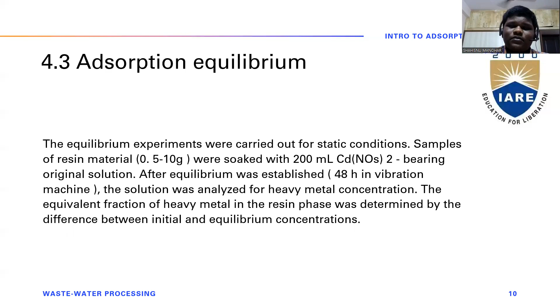Analytical. Heavy metal concentrations were determined by means of flame atomic absorption spectroscopy using a Varian SpectrAA 300 instrument, which has detection limits of 0.001 mg per liter for Cd, 0.01 mg per liter for Pb, which is lead, and 0.0001 mg per liter for Hg. Effluent pH values were monitored using standard electrodes and a digital pH meter 646. Concentrations of organic matter, expressed as TOC, were measured by a Shimadzu TOC 500 analyzer.